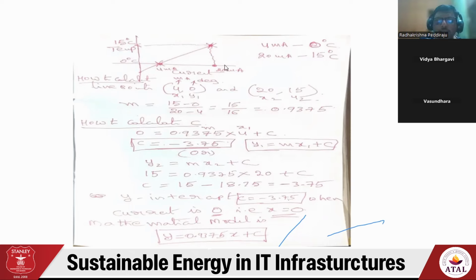15, okay, I'm going to take this one because this is y2, and 0 is my temperature actually set to 15 degrees. The freezer range is 0 to 15. My monitoring, freezer may go to 25 degrees, but I'm not interested. After 15 degrees, if it's there, I should take some action. That's why the cutoff temperature is 15 and starting temperature is 0, I've taken 0 to 15 degrees.